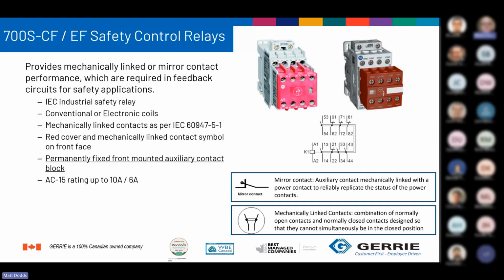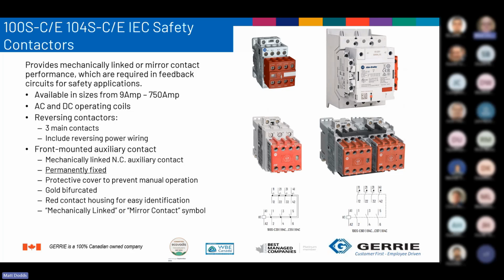Safety contactors, or sorry, safety control relays. They look like contactors. They provide mechanically linked or mirror contact performance, which is required in feedback circuits for safety applications. These have a permanently fixed front-mounted auxiliary contact box, so they are glued on and you cannot order them separately. And then for switching larger current, we have the contactors. They provide that same mechanically linked or mirror contact symbol, again with permanently fixed auxiliary blocks, up to 750 amps.